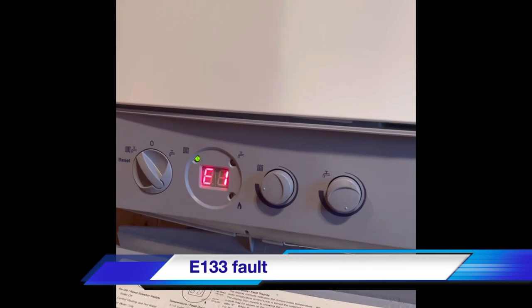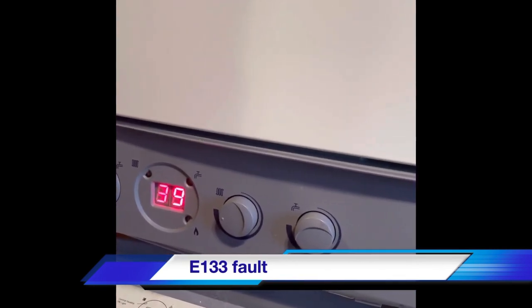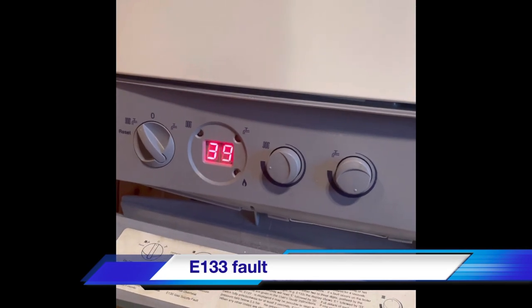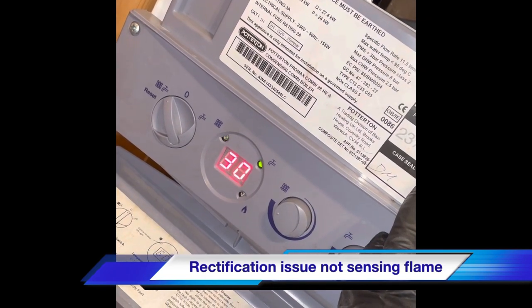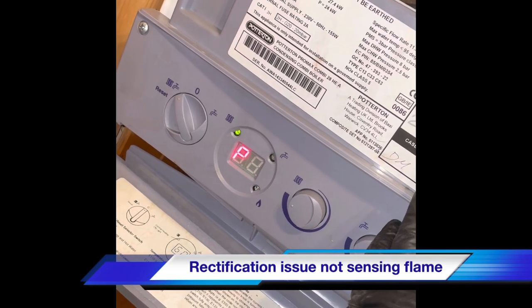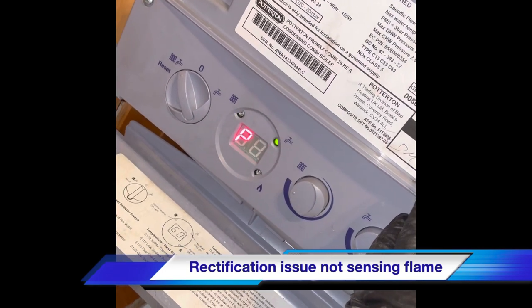We've got a Potterton Promax E133 fault. The customer says the boiler runs for about 20 minutes then goes to fault code. So we'll reset this. There's a detection problem — the boiler is lighting but it's not sensing the flame.